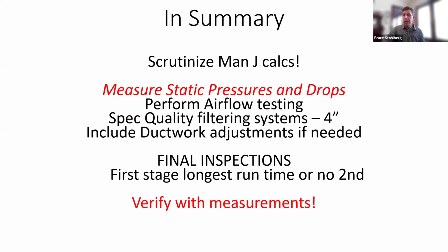Let's see, I would spec out 4-inch filters. If you have room in the return drop and you're replacing the furnace, it's a very good time to add a 4-inch drop. Include ductwork adjustments. If you do static pressure testing and you find that there's a problem, I would go ahead and say, hey, we need to add another supply or get more return. And then, if it's a 2-stage system, try to run it on first stage. If your numbers don't look good on second stage, try to run it on first stage as long as possible.